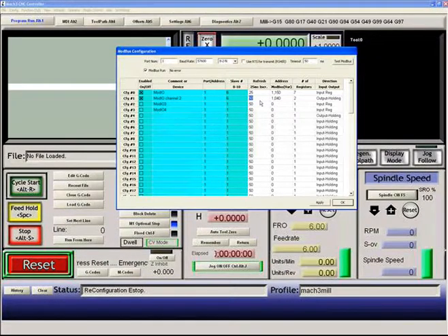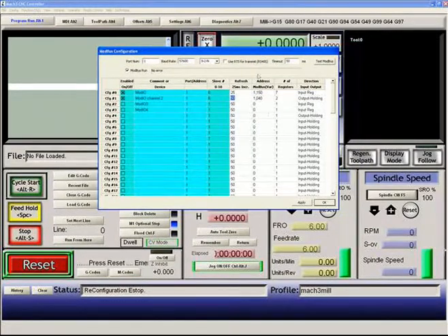You can juggle these refresh numbers around, and you can set as many configurations as you wish on a PLC so that certain words are pulled in faster than others and certain words are pulled out faster or slower than others. What I've told it to do is, starting at address 1040 in the Modbus, fill it with 2 registers.